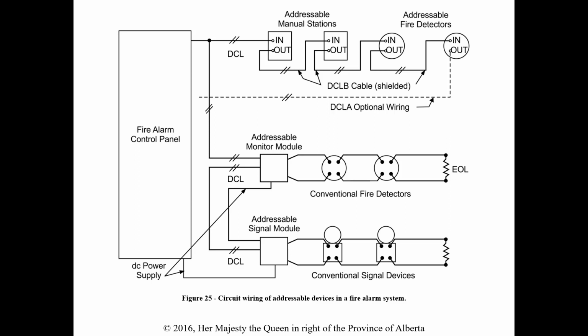Yeah, this is in the module where it says we can. We said in the code we don't want to tap, but this is where it says specifically that DCL-B configurations allow for tap splices under specific conditions described by the manufacturer's engineer. In a DCL-B configuration, as in class B, any addressable devices beyond a break in the circuit wiring can lose the capability of reporting an alarm condition to the CPU. And tap splices cannot be used in a DCL-A or DCL-C. DCL-C is basically just one that goes through more than one fire zone. Okay, that's the difference between DCL-A, B, and C. That's on page 31 of your module. So DCL-B can be tapped in this specific scenario. So addressable class B potentially can be tapped, and we'll go through that in our lab as well.